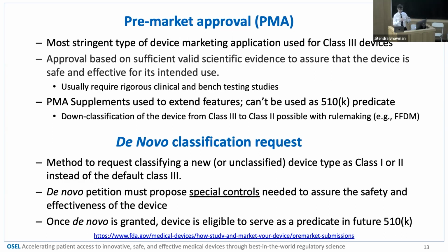And if it's granted, the FDA will create regulations that create a new type of device and will create special controls. That's a few items that have to be completed for this kind of device. And now this device can be used as a predicate in a 510(k) process. Now I'll show an example.